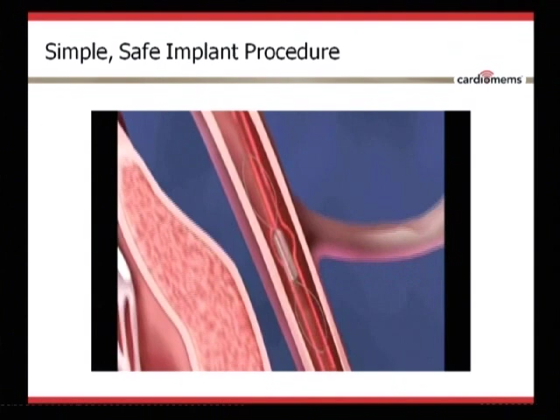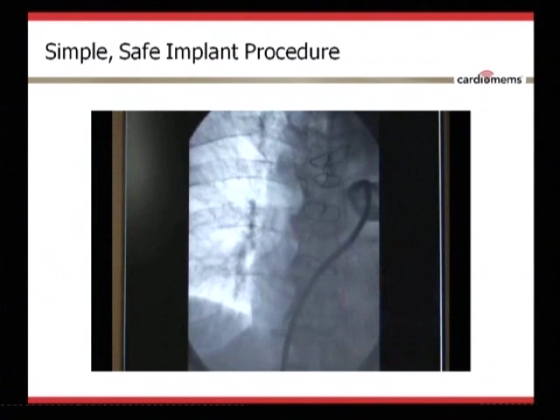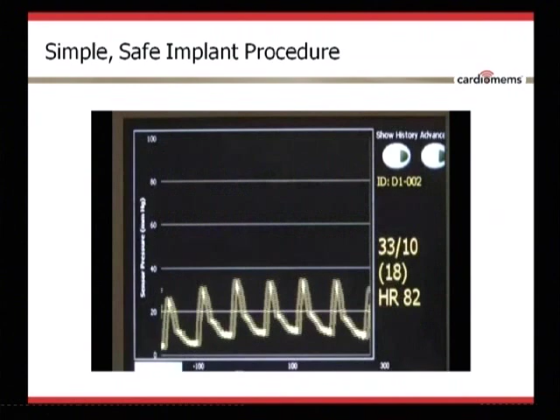Wire loops on the ends of the sensor stabilize it in the vessel and prevent distal embolization. Once in position, the sensor is detected by the external electronics. The external electronics powers and receives signal from the passive sensor using RF energy. The sensor pressure measurement is calibrated to the mean pulmonary artery pressure.